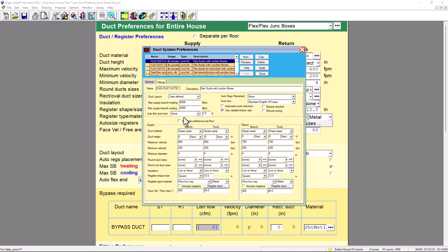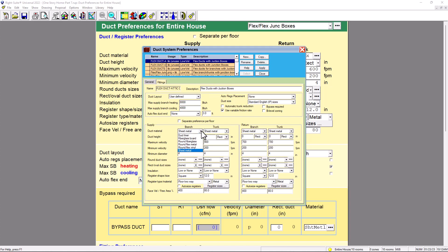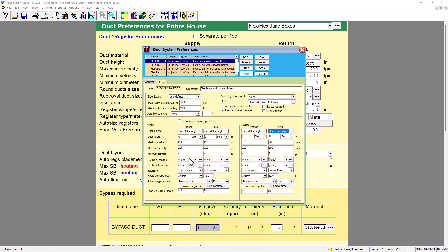Auto flex duct end - we're going to put None. Now what we have here is the duct material. Since we're talking about flex ducts, we're going to put everything flex: round flex vinyl for branch, round flex vinyl for trunk, round flex vinyl for return branch, and round flex vinyl for return trunk. For duct height, let's leave it at zero for now. But this is the most important part: maximum velocity and minimum velocity. I don't want anyone to get confused on this part, so I'm going to pull up tables from Manual D.